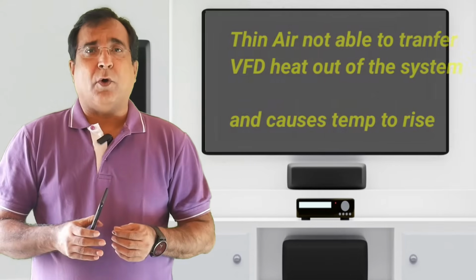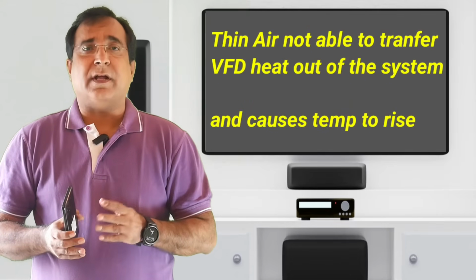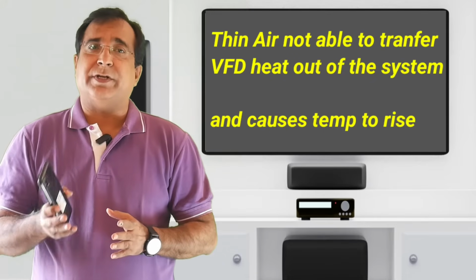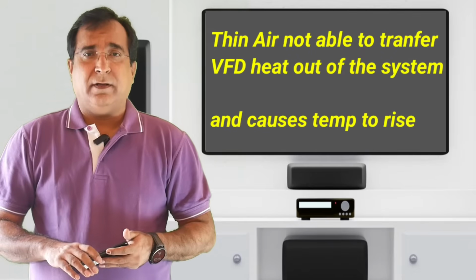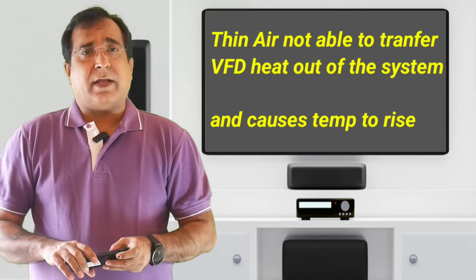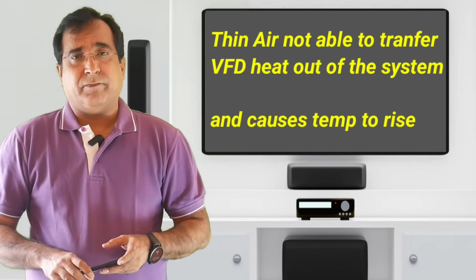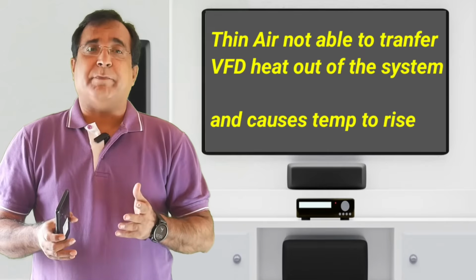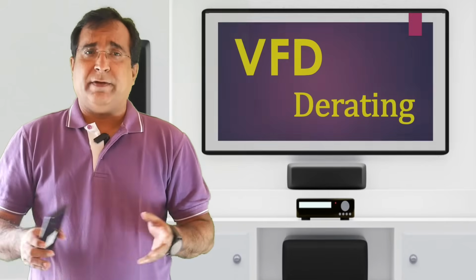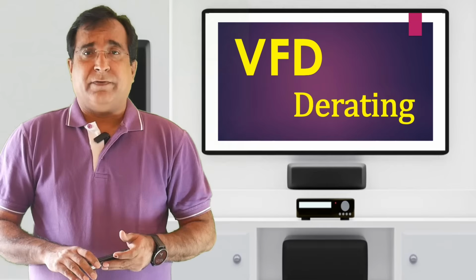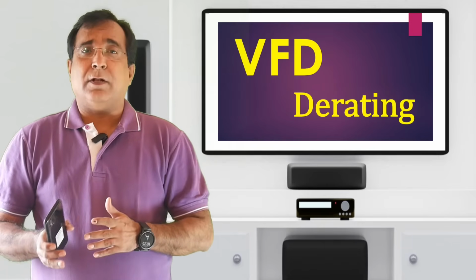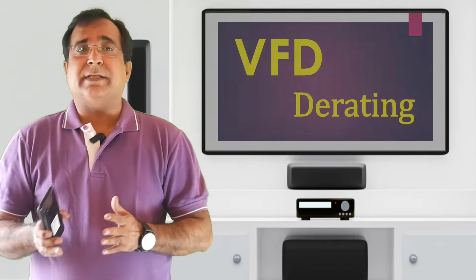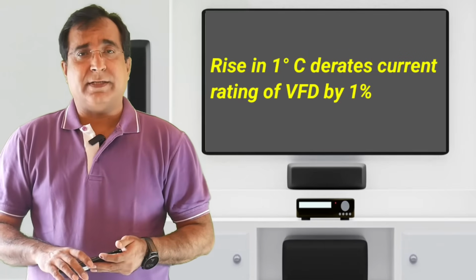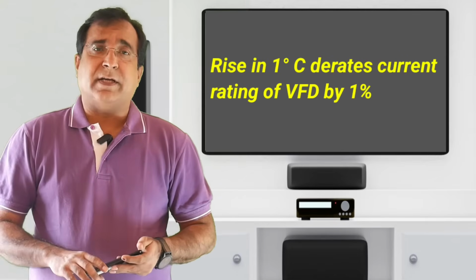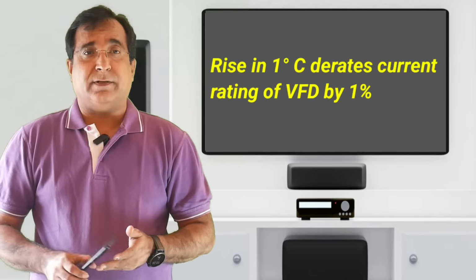This thin air, when blown over the IGBT heatsink, is not capable of transferring the generated heat out of the VFD. That means the air cooling efficiency of the VFD gets reduced and it raises the temperature of the heatsink and hence the VFD. Now this factor is mentioned in the VFD data sheet. But as a general rule of thumb, VFD current rating is derated by 1% per degree Celsius. In some of the VFDs, current rating reduces by a factor of 2%.